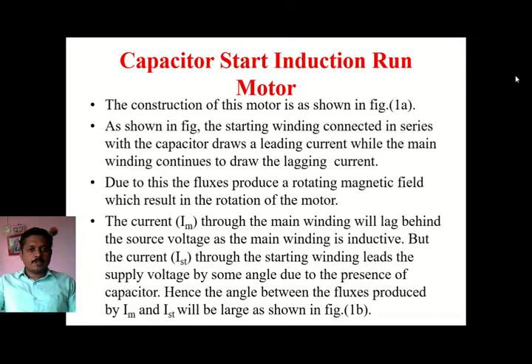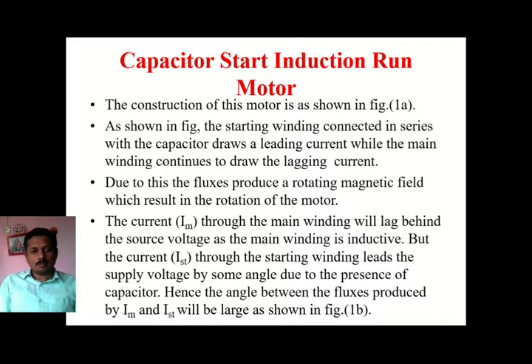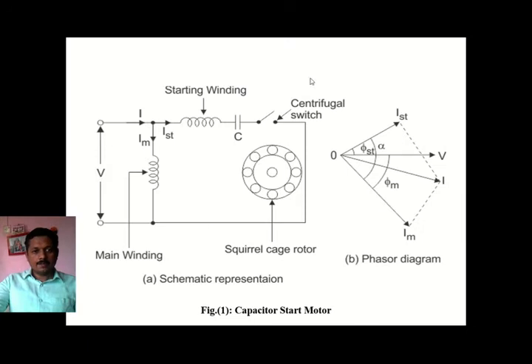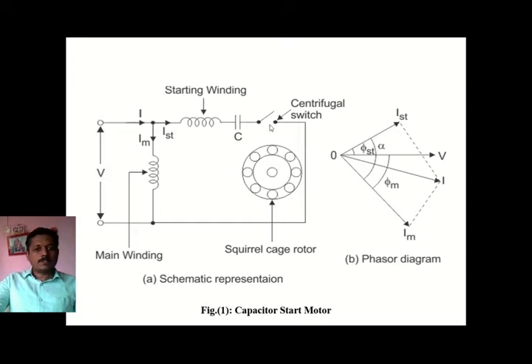First: capacitor start induction run motor. As its title says, it has a capacitor only in the starting condition, but in running condition it will run on the inductor, meaning the winding. I will first explain this with a diagram. The main winding has an inductor-based winding, and in the auxiliary winding we have a capacitor and a centrifugal switch.